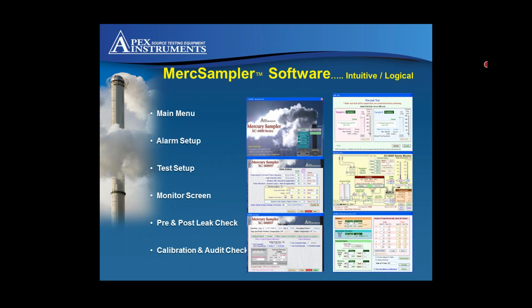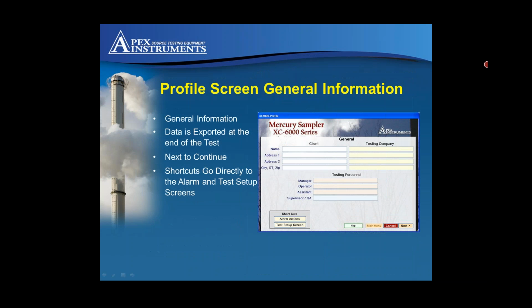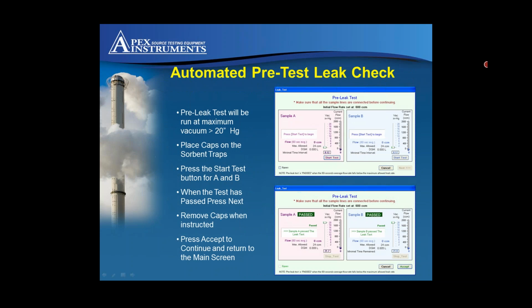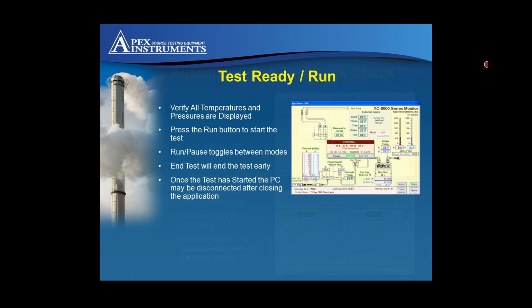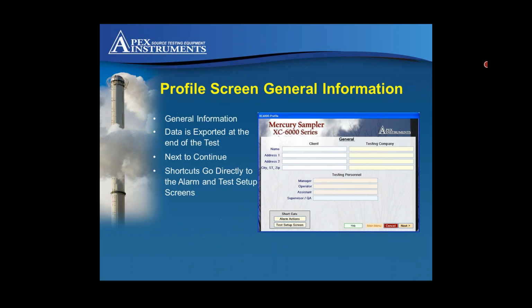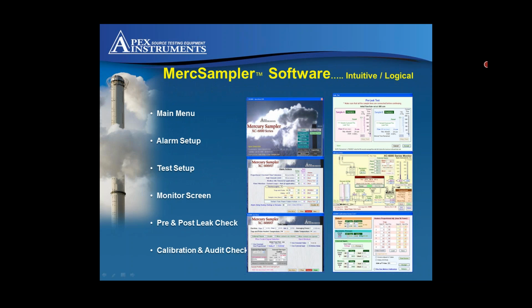The one in the bottom left corner is your actual test setup. Okay. The bottom screen there is where you tell it what your sample rate is, what the external flow signal will be, what you want to set your heater temperatures to, and how to handle external pause signals. That's pretty much where everything is set up.